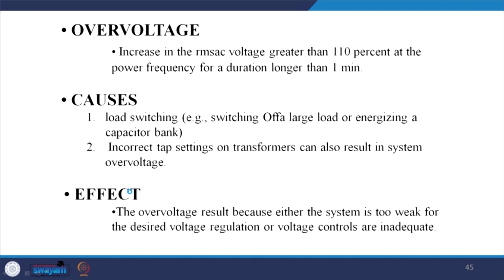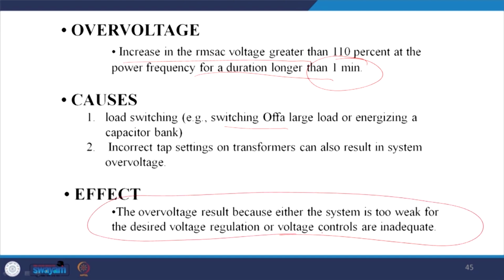First, let us define it. Over voltage is an increase in the RMS value to greater than 110%, that means 10% more than nominal, at the power frequency for longer than 1 minute. The cause may be switching, for example switching of a large load or energizing a capacitor bank. Incorrect tap settings of the transformer can also result in over voltage. As an effect, the system may be too weak for the desired voltage regulation, or voltage controls are inadequate. So, these are the reasons for it.